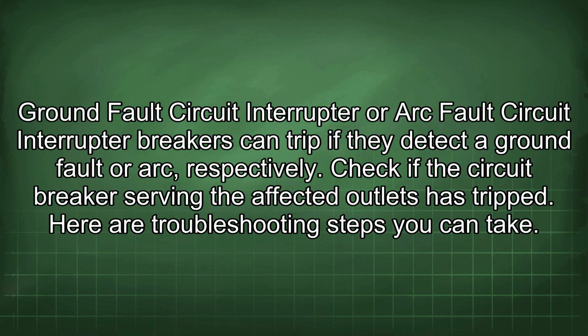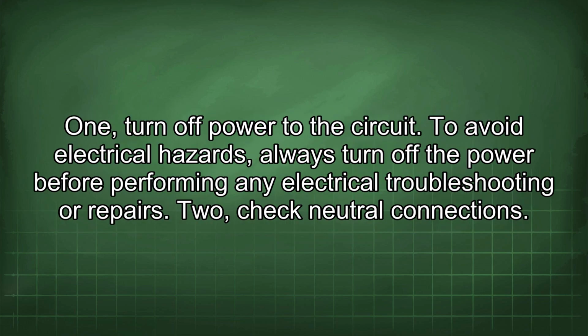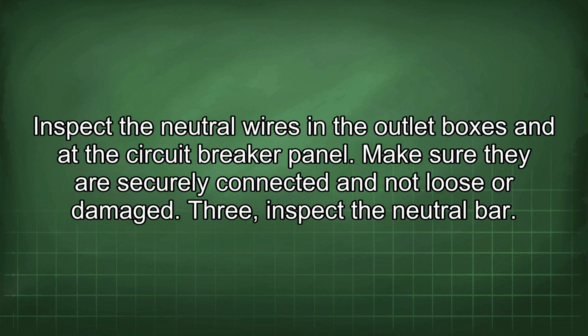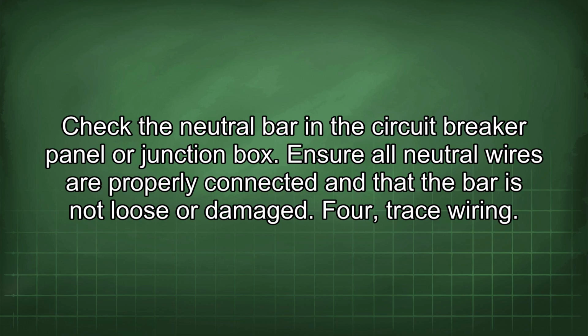Here are troubleshooting steps you can take. 1. Turn off power to the circuit. To avoid electrical hazards, always turn off the power before performing any electrical troubleshooting or repairs. 2. Check neutral connections. Inspect the neutral wires in the outlet boxes and at the circuit breaker panel. Make sure they are securely connected and not loose or damaged. 3. Inspect the neutral bar. Check the neutral bar in the circuit breaker panel or junction box. Ensure all neutral wires are properly connected and that the bar is not loose or damaged.